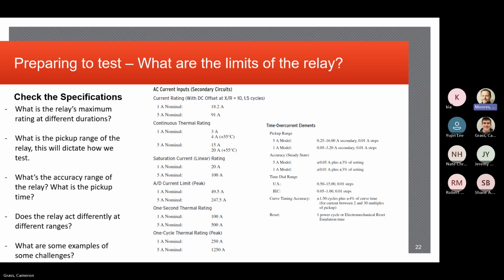The minimum pickup isn't going to operate an output that's going to trip a breaker or a device, because we want to make sure it trips based on the relay time curve, the 51, we'll call it T element. That's going to be in the trip string. That's going to be in the output that's hardwired to trip a device. So we would make sure that that does trip that one. So that's the reason for the two different types of output testing.